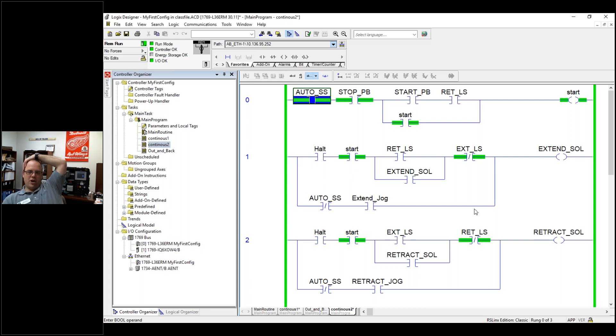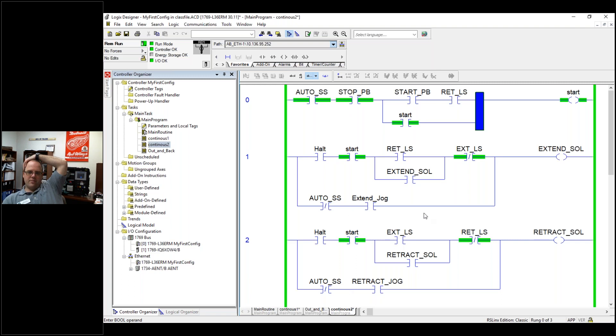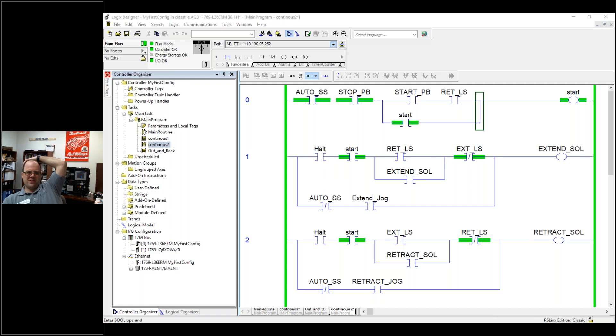The idea is: think about jogging, think about what needs to be there. To give you some tricks — initial conditions go once inside the seal-in; everything that always needs to be true goes outside. Then I can use a start bit to power everything on. I can use a bypass around my automatic section to create a jogging setup. Thank you for your time — I hope this was kind of helpful.